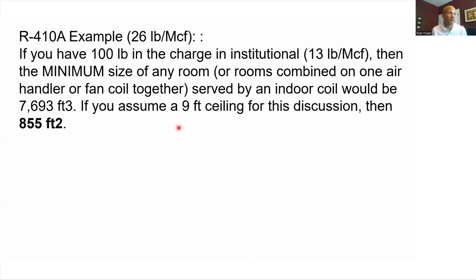So it does make it a lot harder. But in any case, doing the math with 100 pounds of refrigerant, which is obviously a big system, but most VRF has a lot of charge, with my 13 pounds per million cubic feet limit, I could do the math and find out that the smallest area that I could serve would be 7,600 cubic feet. For a 9-foot ceiling, which this building had, that means 855 square feet. If I have any zones that are less than 855 square feet, I have to take them off the VRF system, or I have to combine those two rooms into one room so the square footage is larger. We've always done that math on VRF. We've always had that struggle with the small rooms. We'll take it off the VRF and give that one a PTAC or a single mini split or something like that. It's always been going on.